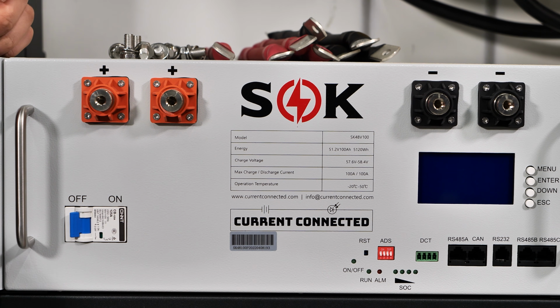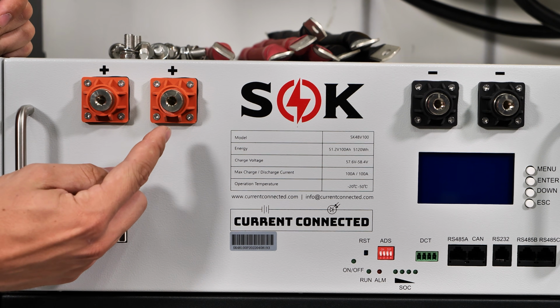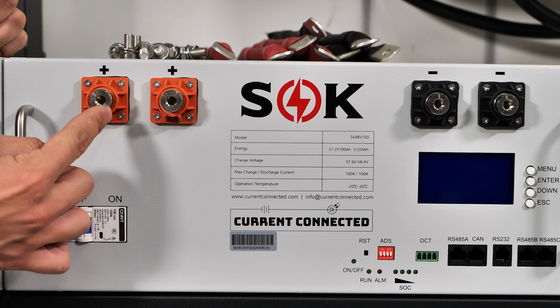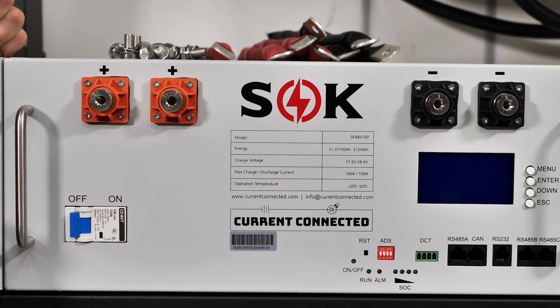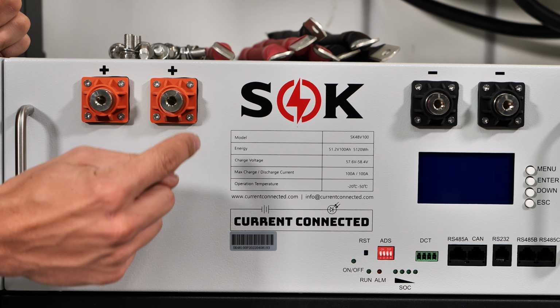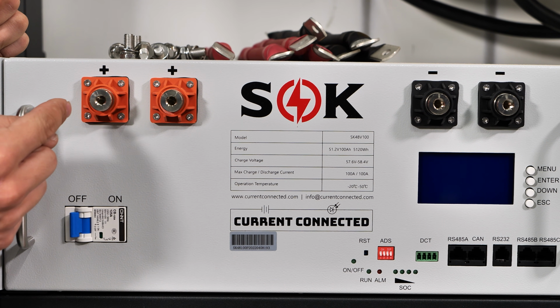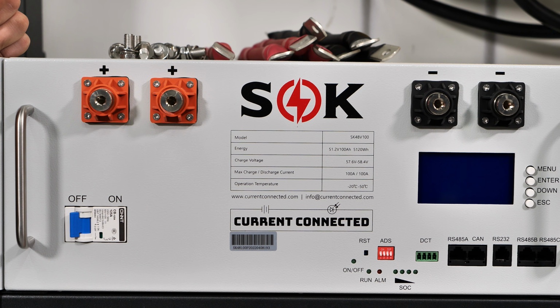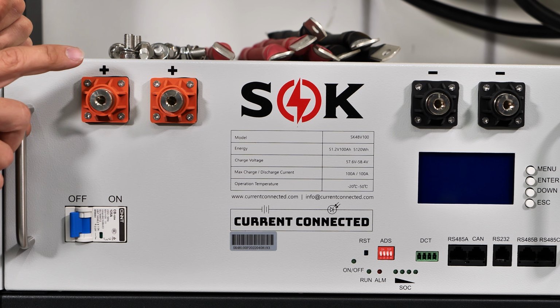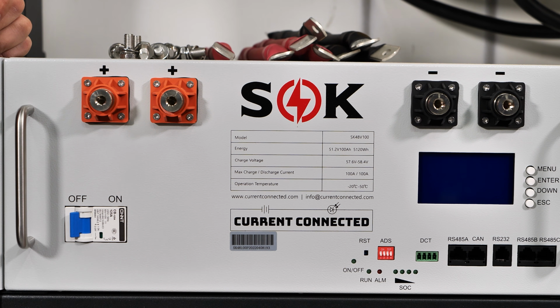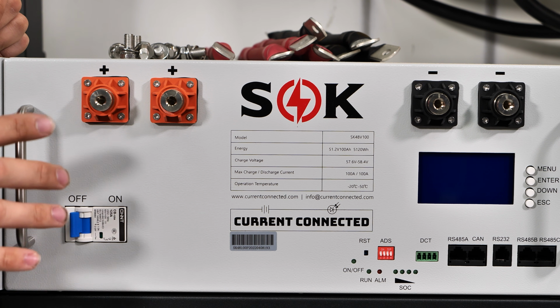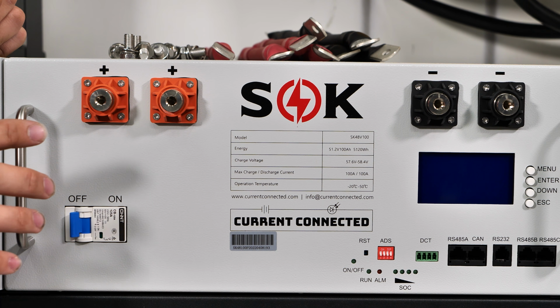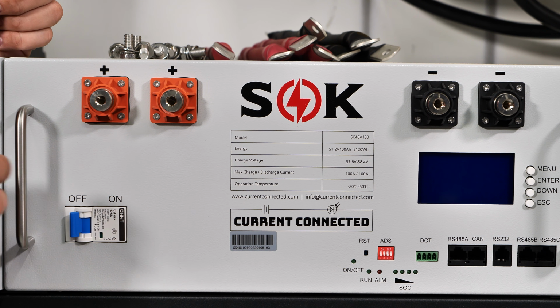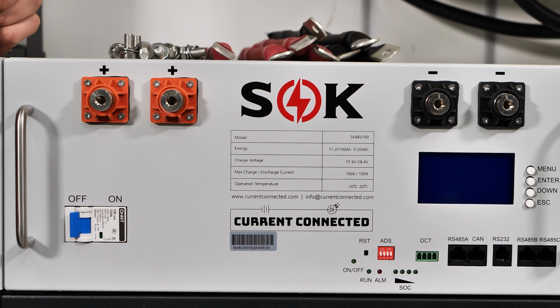Now, one thing that may not make sense yet, but is worth noting, the feed-through current from one terminal to the other is 350 amps. That means if we had 350 amps coming through our cable, going through the battery and back out, we would be fine, but if we had more than that, it would be a problem. This is an important consideration if you're doing racks with large amounts of batteries. Let's say it's not the 5-slot SOK rack, let's say it was an EIA server rack. That's when it would be important to take note of that feed-through current. But in today's example, we're not going over 100 amps, so feeding through the terminals of the battery is no problem.